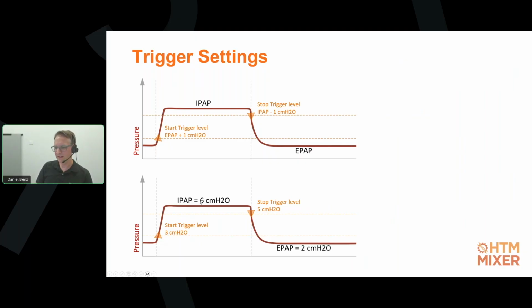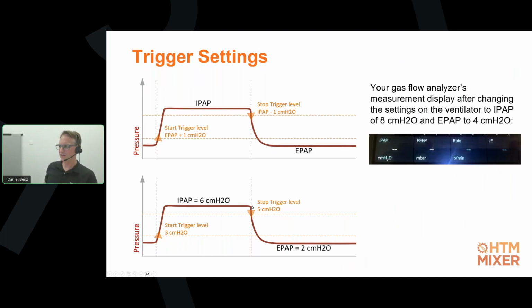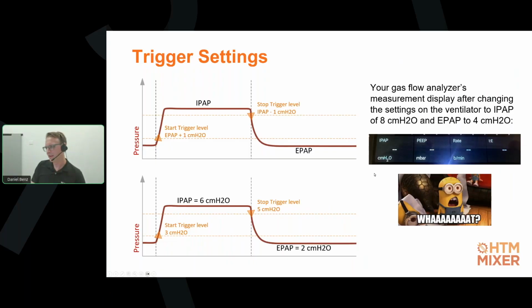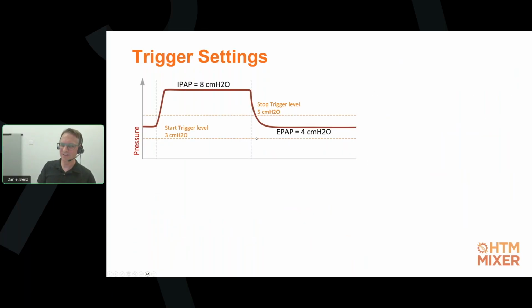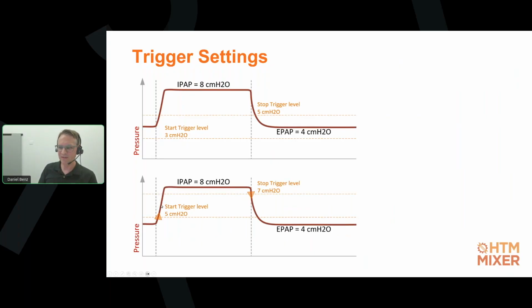So let's say you have the settings IPAP 6 and EPAP 2 centimeters, then you probably have your start trigger at 3 and your end trigger here at 5. And this is going to work well. However, let's say you have to change your settings on the BiPAP machine, and you change IPAP to 8 and EPAP to 4 instead of 6 and 2, then your gas flow analyzer might just say, well, not measuring anymore. The reason is that the settings of the triggers are now dependent on the settings of the ventilator. So if we take a look at the graphics with our previous settings, now our waveform is shifted up and it's no longer going to trigger because that lower level here is not going to be reached anymore. So here, based on the settings of the ventilator, we would have to correct the settings of our triggers to actually have measurements again.